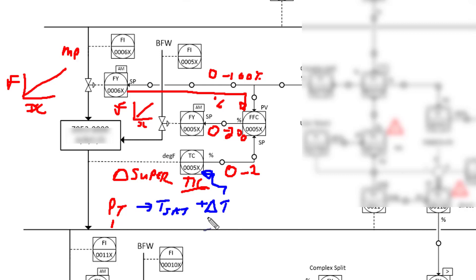What we do is we calculate and then we have a delta, and that becomes the set point for this controller. So you give the operator, or you show the board operator, a degree of superheat. You give them what we call a HIC or we call it a TDIC. And the minimum that they have would be around about 8 to 10 degrees Celsius. In other words, you want to control this temperature here at least 10 degrees Celsius above the saturation temperature at the given pressure on this line. And this entire thing is now linearized and tuned for one scenario, and that solves the entire heat and material balance for all conditions.